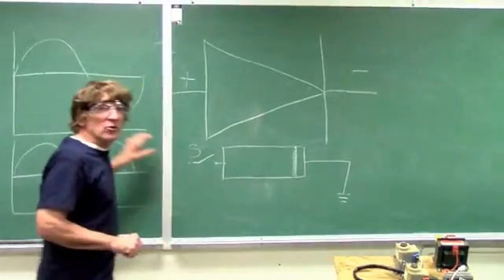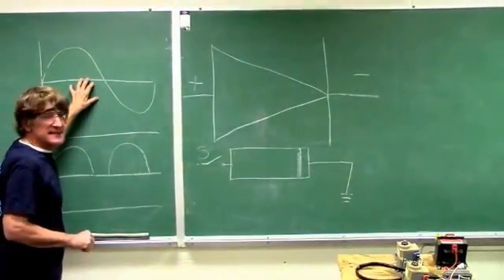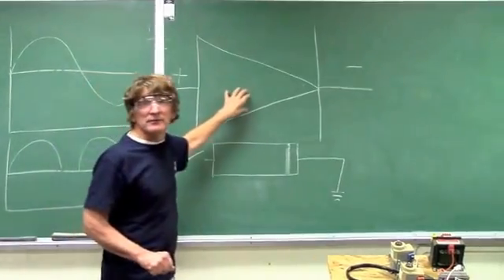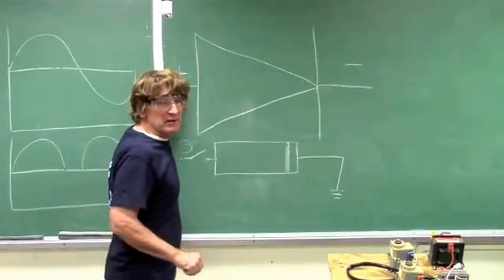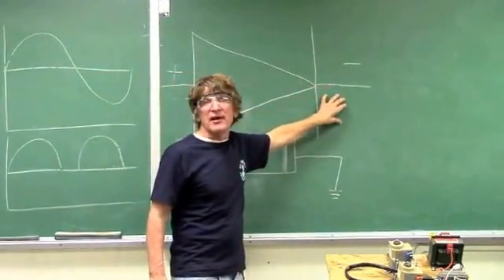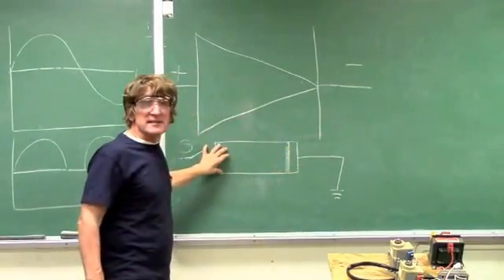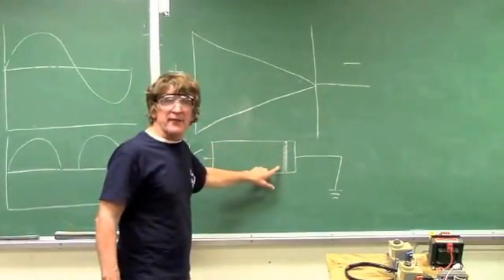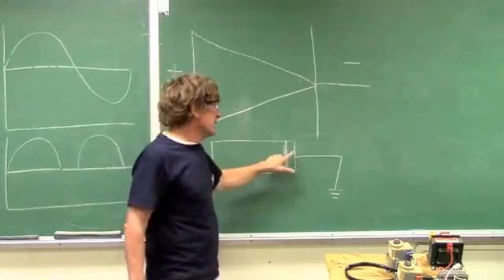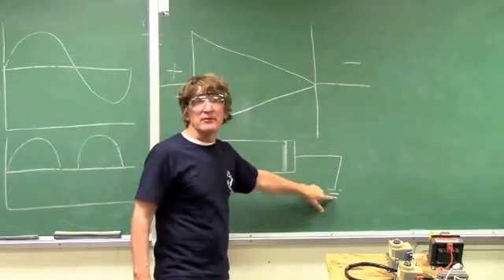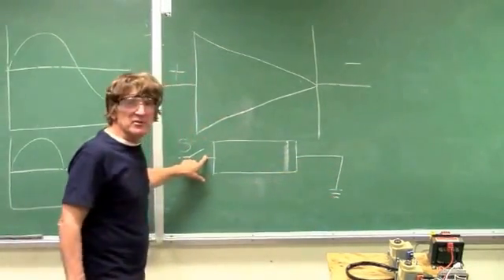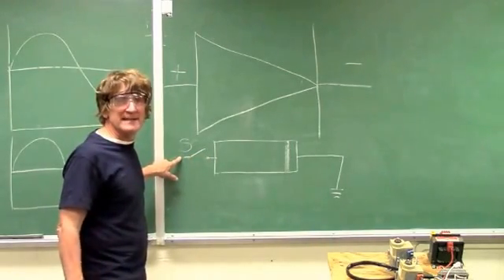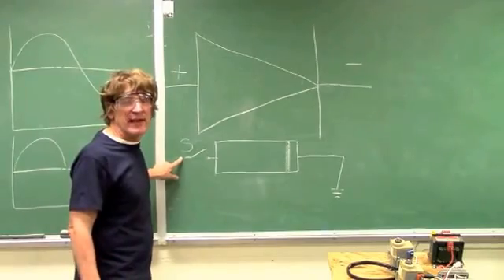In order to change it from an AC signal to a pulsating DC signal, I add a diode. The anode is the plus sign, the cathode is the negative sign. This bar right here represents the cathode — in this case I'm going to send that straight to ground. The other side represents the anode. I put a switch in it, and this goes to wherever my sensor line is that's used to sense flame.